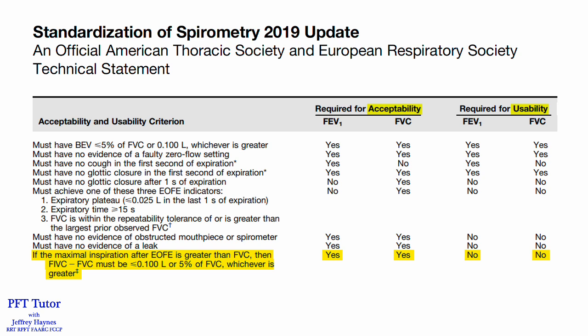In the 2019 ATS-ERS spirometry standard, submaximal inhalation error was added to the acceptability criteria. Specifically, for a test to achieve an acceptability score, the difference between the forced inspiratory vital capacity and the forced expiratory vital capacity must be equal to or less than 100 mLs, or 5% of the vital capacity, whichever is greater.